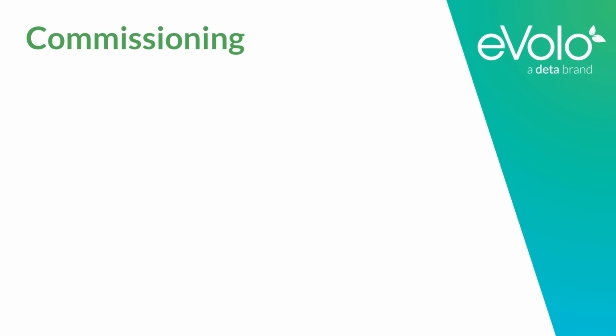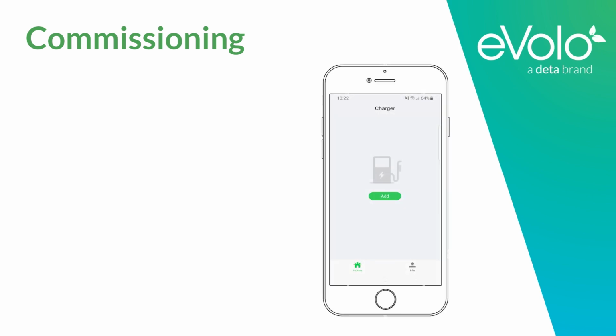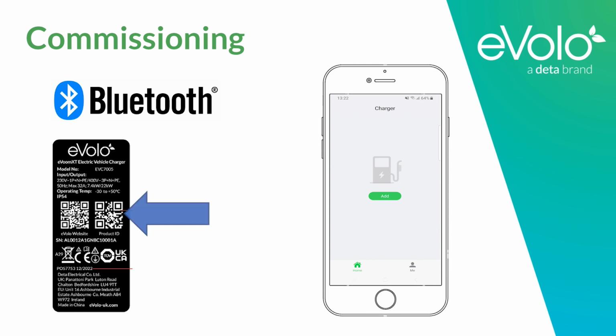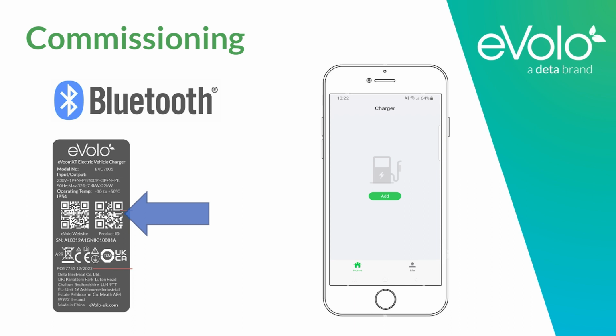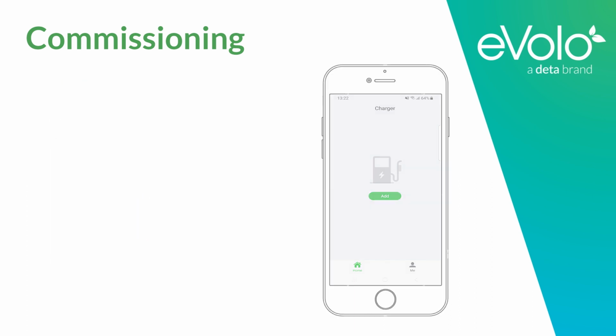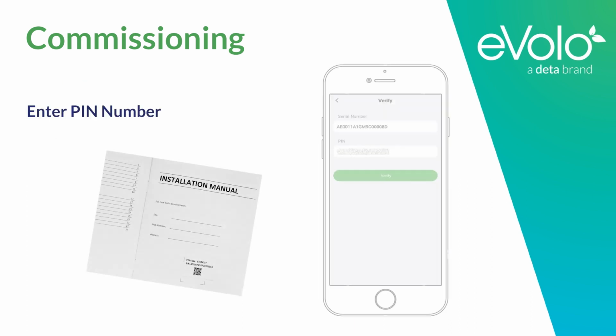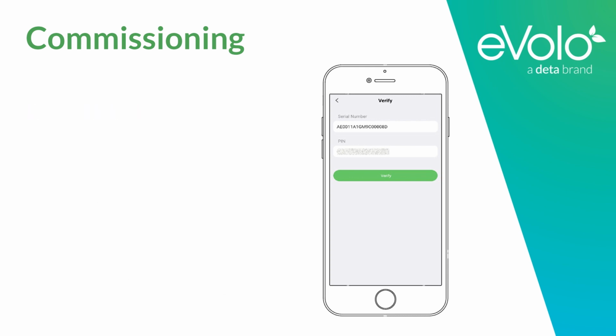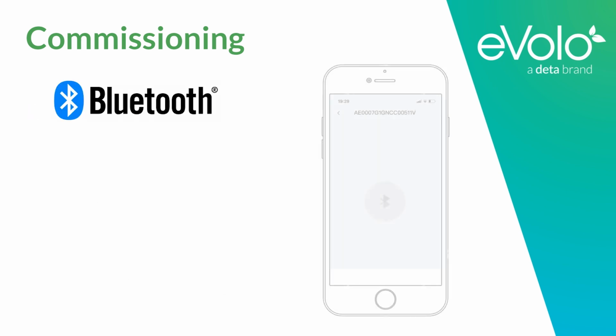If you are commissioning a charge point where internet connection is not available, ensure Bluetooth is enabled on your device and you have a 4G connection. When on the app, press Add and scan the unique product ID QR code which is on the product rating label. To commission a charger, locate the serial number and enter the PIN which can be found on page 3 of the manual. Next, you will need to connect to the charge point using Bluetooth.